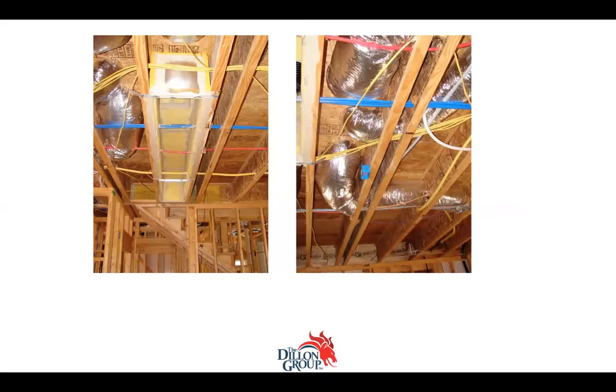And I'd be curious about your perspective on this one, because what they did was the HVAC contractor came in and roughed in the return. This is basically where the return grill is going. It's going to be a massive return grill, and it connects at the top. There's a chase that punches down through the top of this. But along the way, the plumber decided he was going to run his PEX lines right through this return duct, and then his gas line right through this return duct.